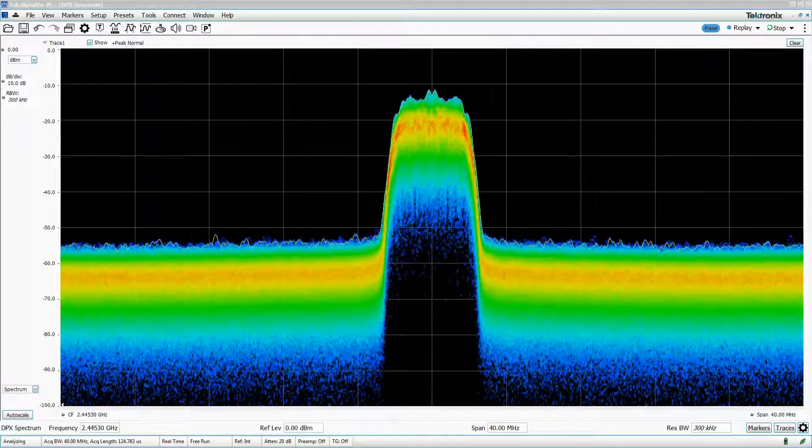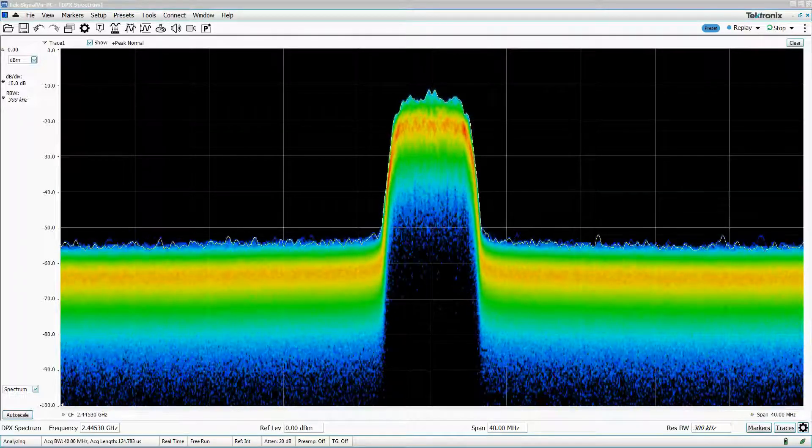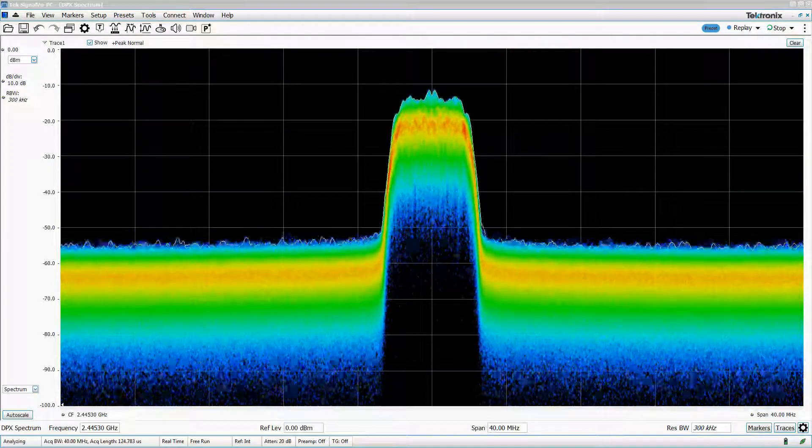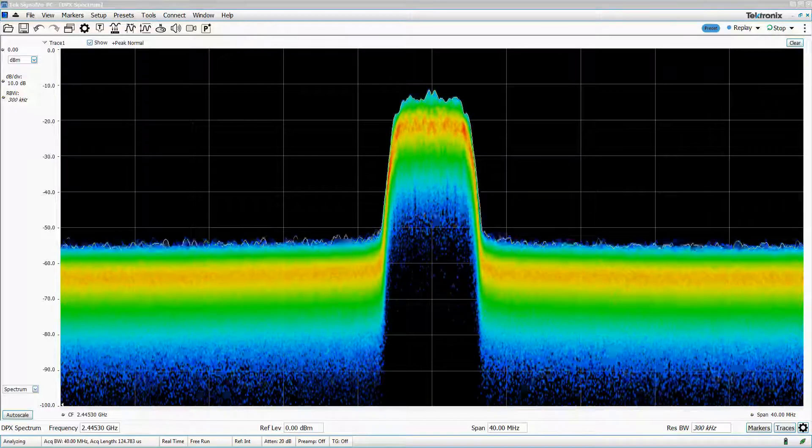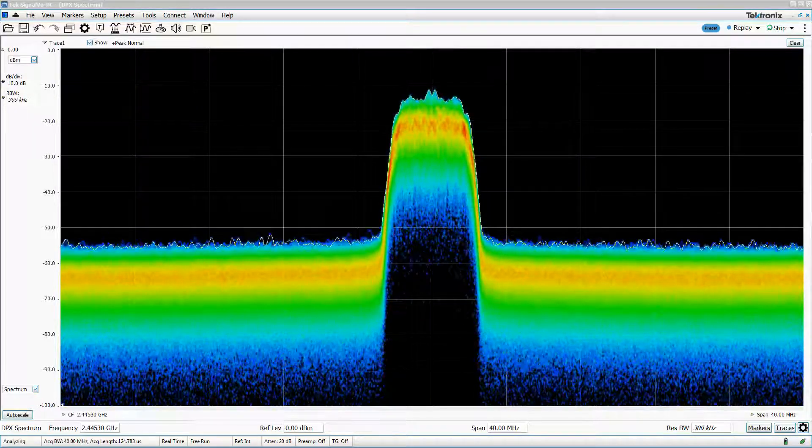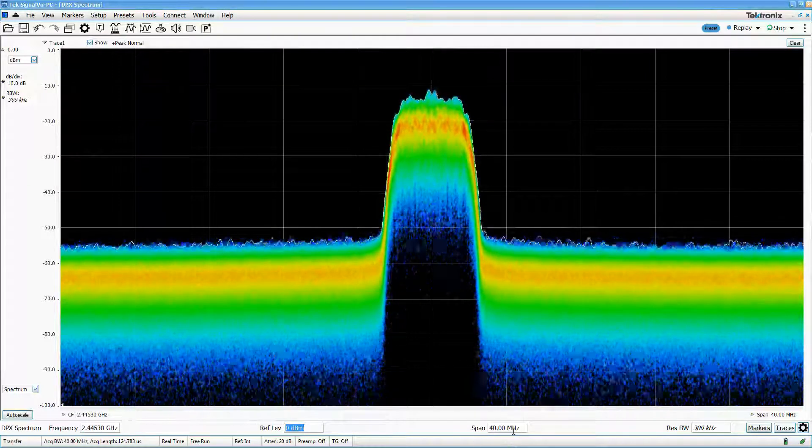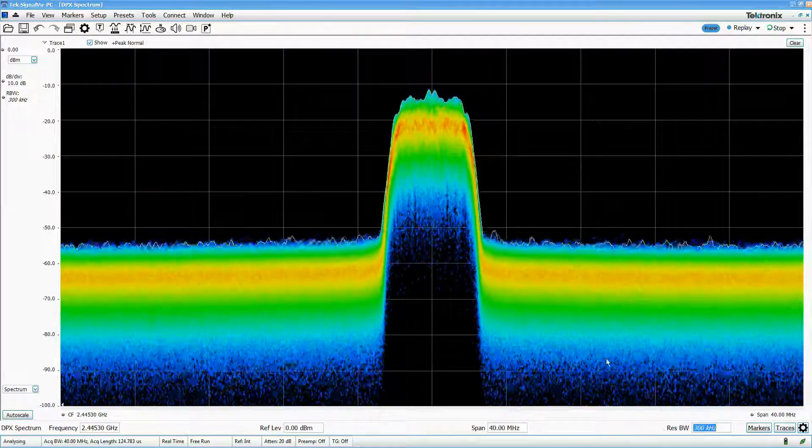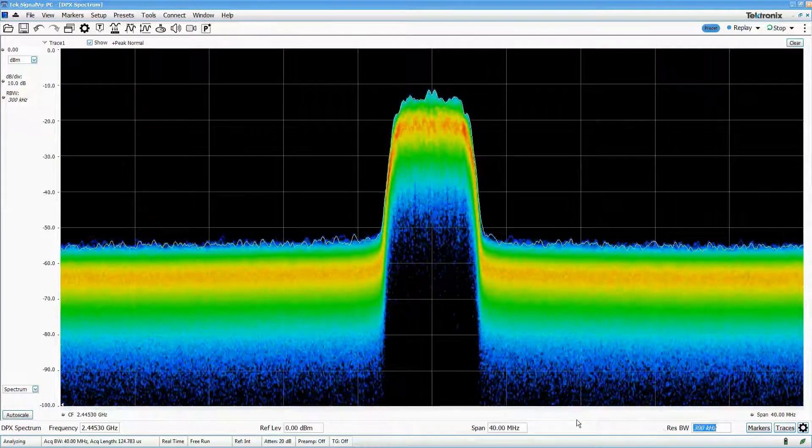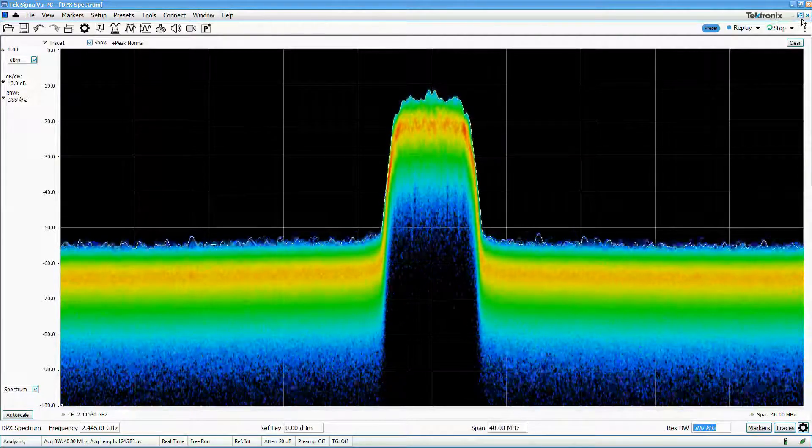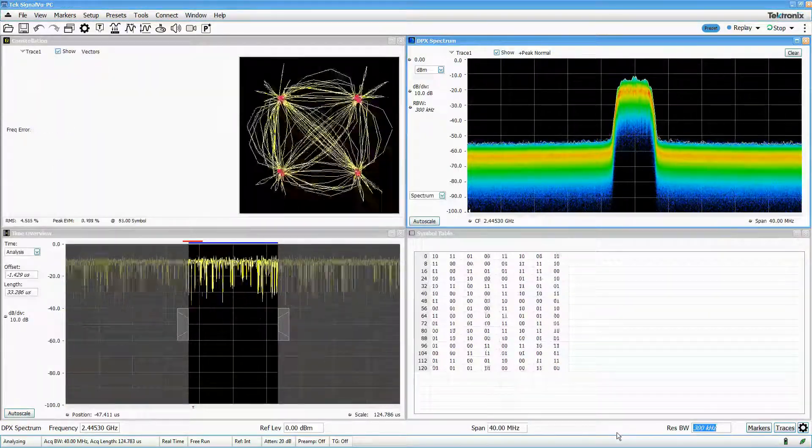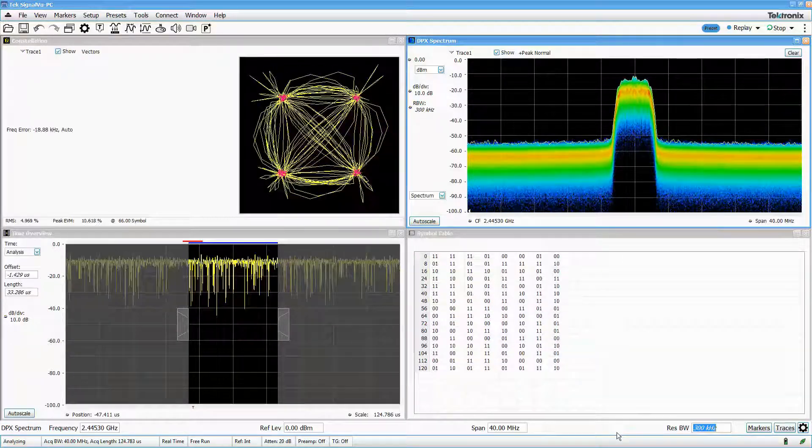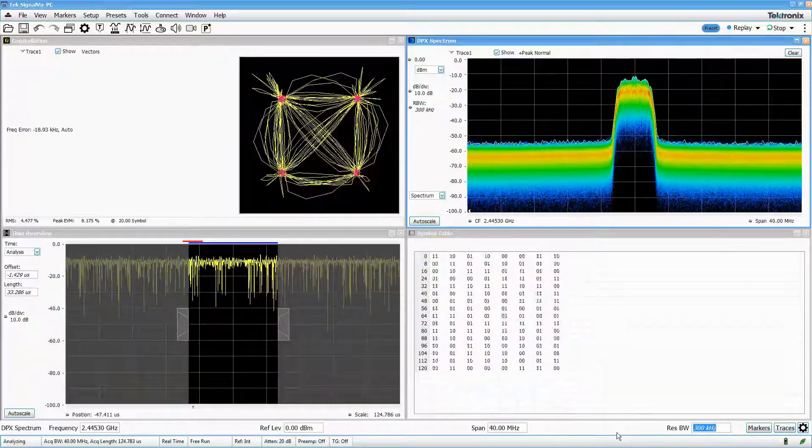There is a common misconception that real-time spectrum analysis is complicated and narrowly focused. In reality, using the real-time capabilities of Tektronix instruments is almost identical to using them for legacy spectrum analysis while providing significantly more information to the user. An added benefit is that you can have the DPX display running while performing other measurements to make sure your signal environment isn't changing without your knowledge.